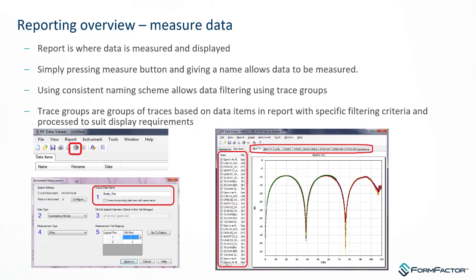When we think of plotting data and plotting S-parameters, we call that a WinCal report. A WinCal report has nice features in that it can help you very easily overlay data for comparison. As you can see on that bottom right-hand graph, there are maybe 20 different waveforms stacked on top of each other. You can examine frequency point by frequency point how things are differing, put markers in place — it's really quite a flexible S-parameter viewer and calculator.